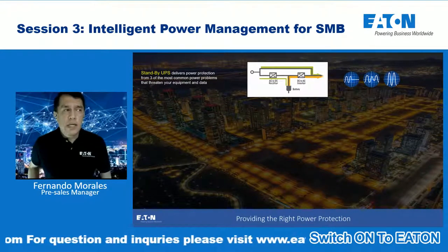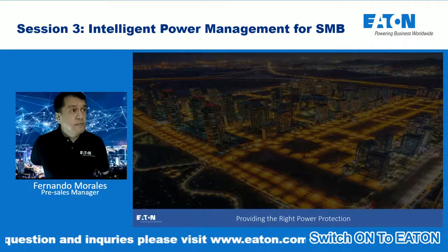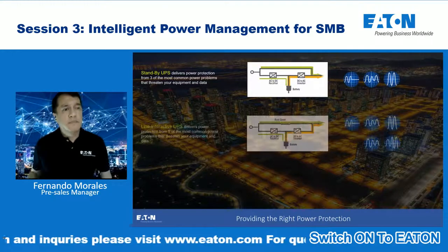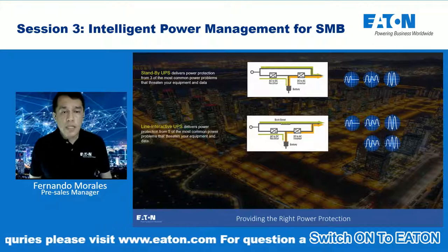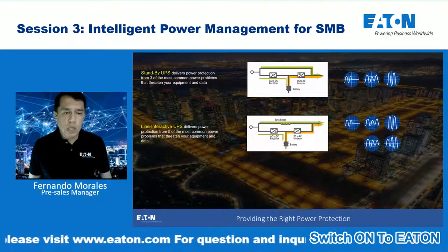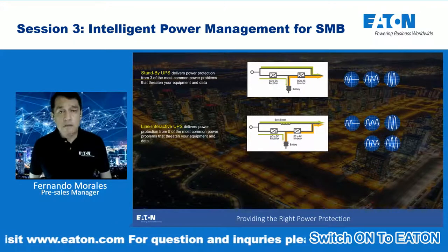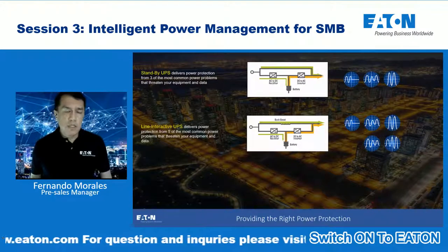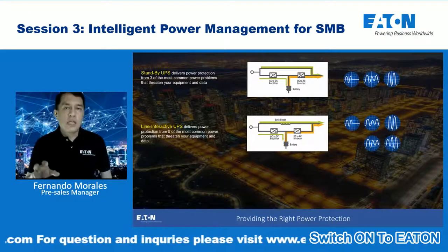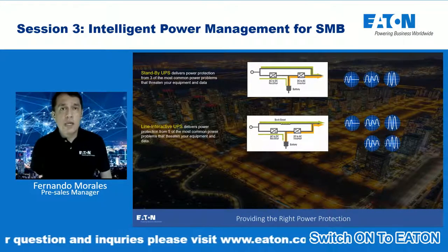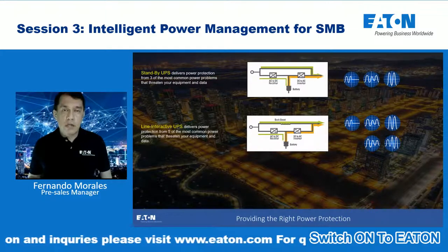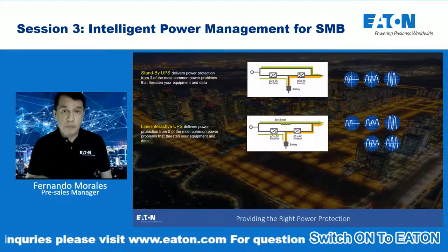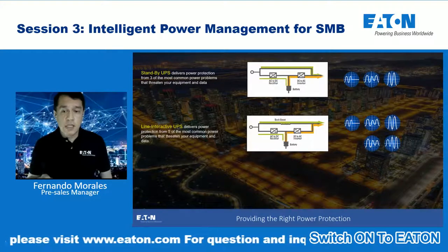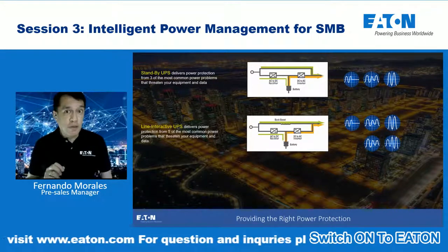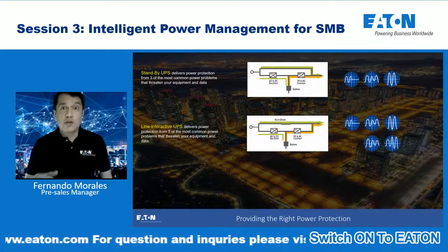And then the other type of design under a single conversion UPS is what we call the line interactive UPS. The only difference between the line interactive and standby UPS is that a line interactive UPS has a built-in AVR inside, but it is not functioning or working continuously.